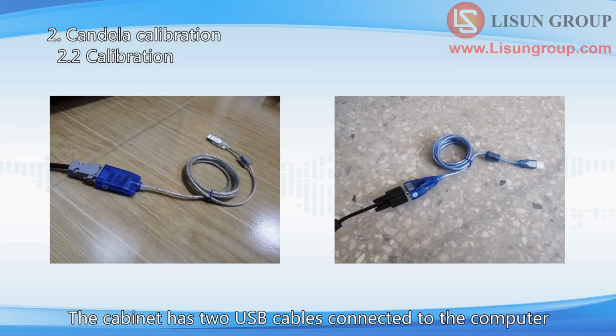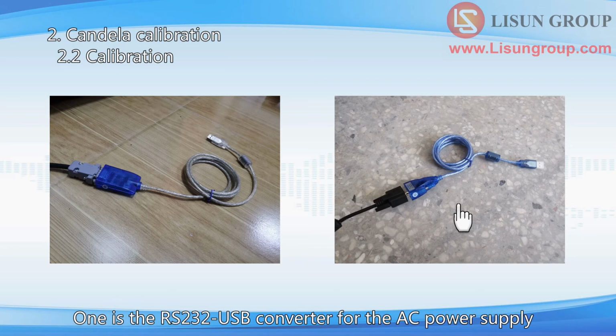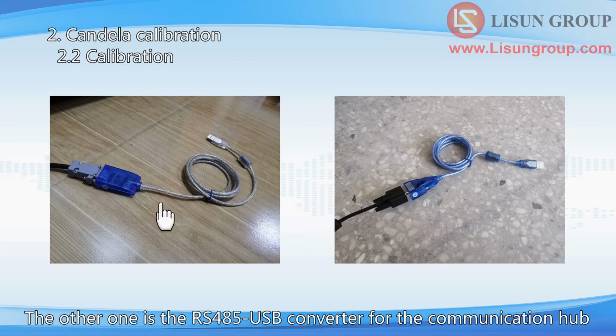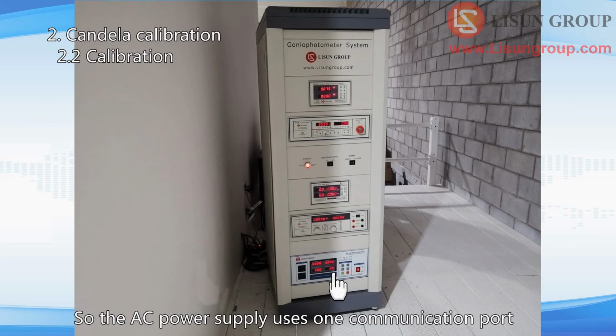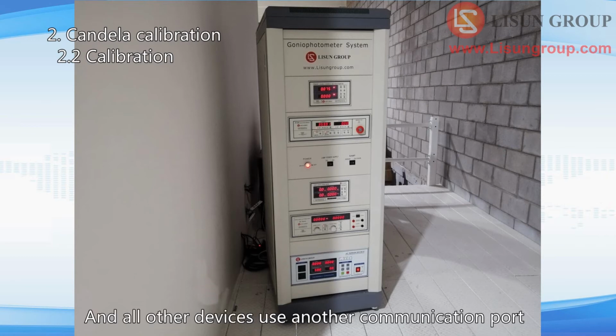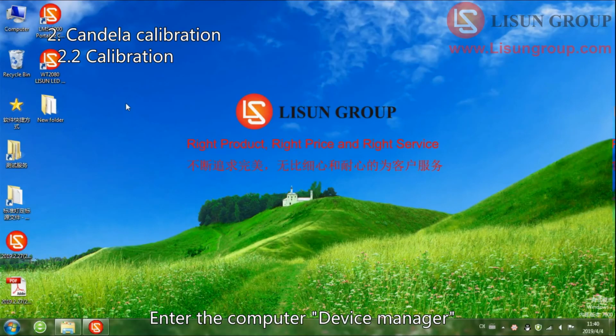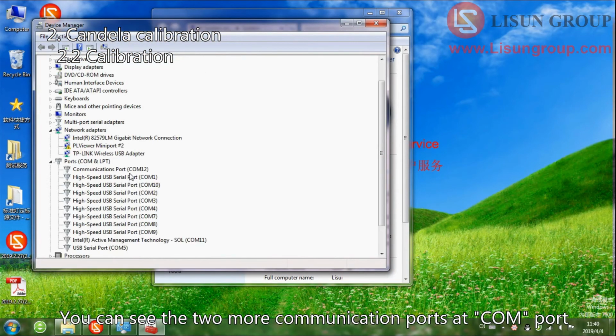The cabinet has two USB cables connected to the computer. One is the RS-232 USB converter for the AC power supply. The other one is the RS-485 USB converter for the communication hub. So the AC power supply uses one communication port, and all other devices use another communication port. Enter the computer device manager. You can see the two more communication ports at COM port.